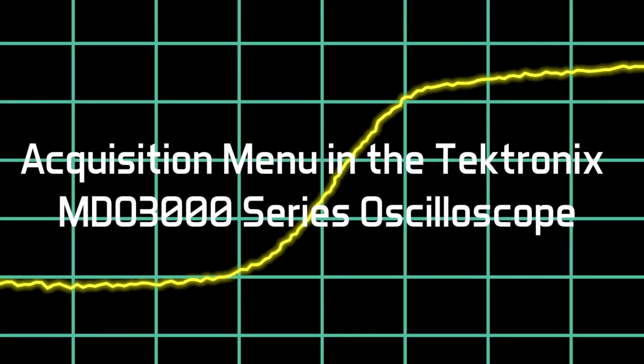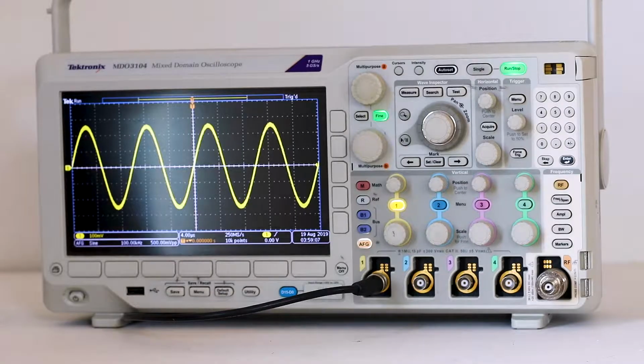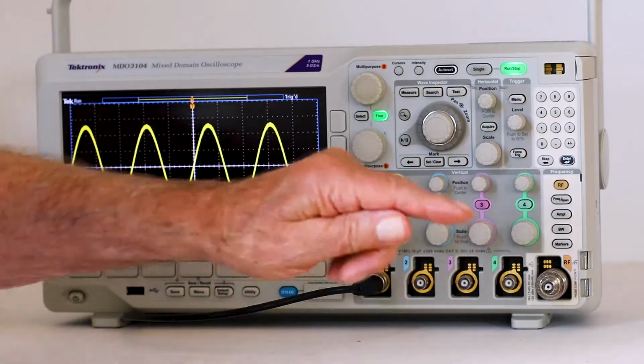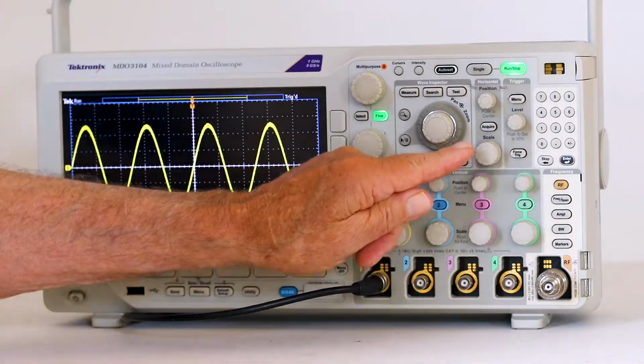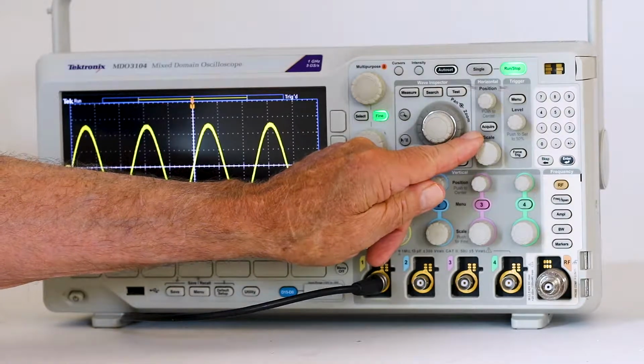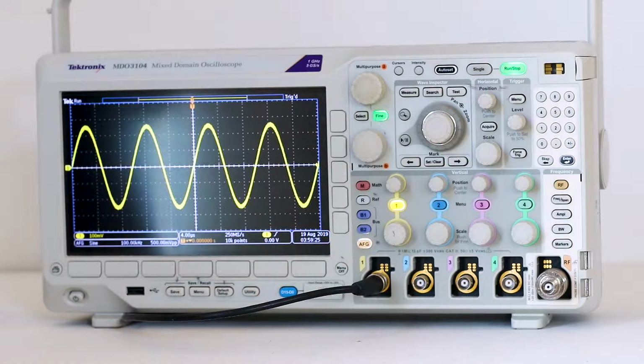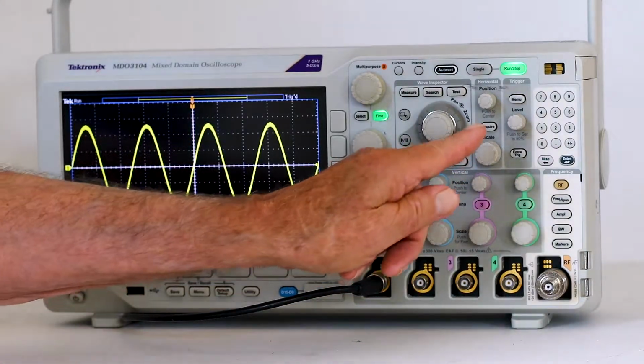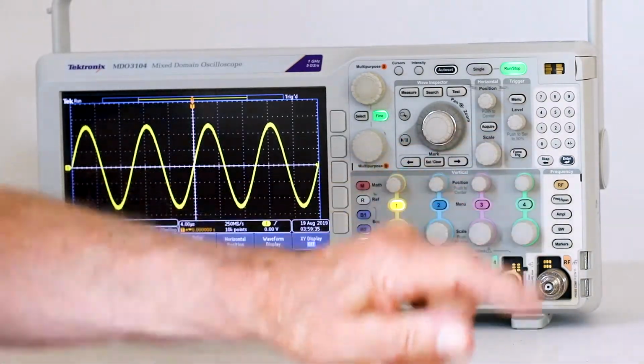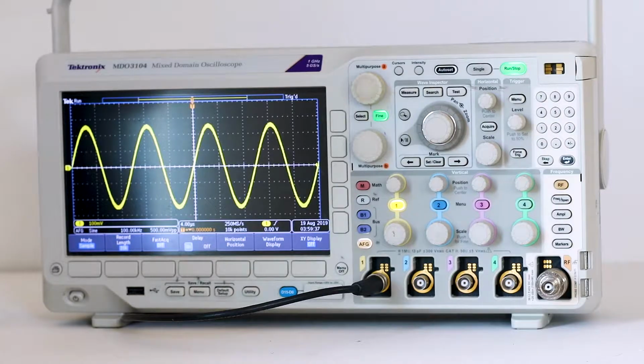Today, in a Tektronix MDO3000 series oscilloscope, we'll see what happens when we press Acquire. This small button is located on the right side of the front panel between the horizontal position and scale knobs. It is not a lighted button and not very prominent, but it is the gateway to a huge amount of functionality. First, we need a signal to work on.